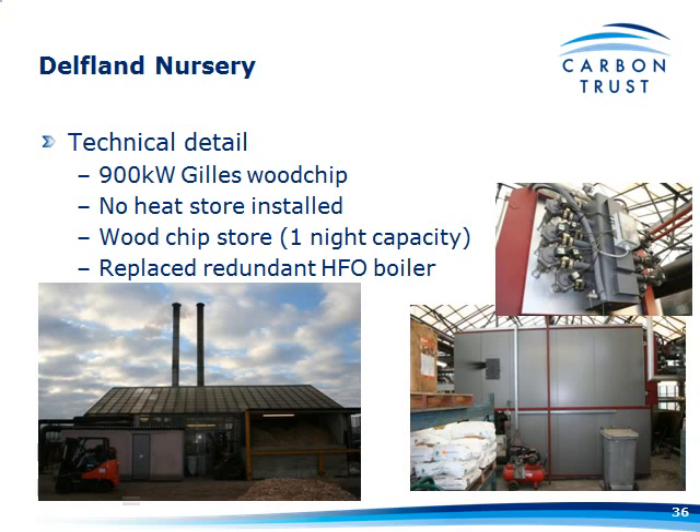A slightly different approach now — Delfland Nurseries, the plant raisers. They've installed a 900-kilowatt Gilles wood chip boiler, now in its third season. This has no heat store attached because they couldn't afford one at the time. They've essentially fitted it all into the existing boiler house — a wood chip store at about one night's capacity, which they refill over the morning and day. It actually fitted in the footprint of a redundant heavy fuel oil boiler. The wood chip itself is kept outside and delivered regularly — they drive up and tip it into the store.